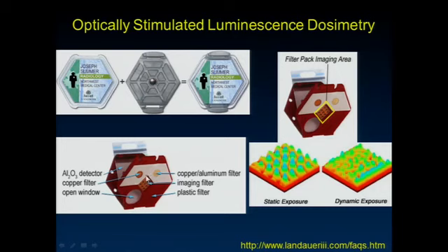And then notice we've got what looks like a little grid right here. It is a little grid, this little imaging window that they call it. Here's a static exposure through the imaging window, and here's a dynamic exposure. Notice in the static exposure, you get these little ski moguls almost, and they're very uniform in their structure. This is how, with that dosimeter, it's determined that you accidentally left your dosimeter sitting in the fluoroscopy room on your lead for the last 2.5 weeks. It gets a static exposure because it's not moving around in the room when that occurs, okay?